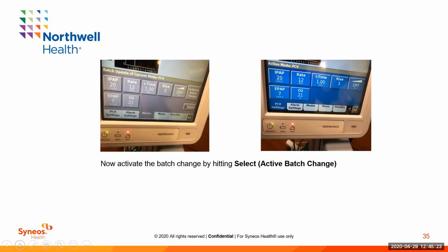Thank you. Okay, so here we have a picture of the batch ST, batch pressure control ventilation settings that Northwell is using. We have inspiratory pressure set at 20, the respiratory rate of 12, inspiratory time, 1 second of breath is pressure over time to activate a volume. We have a rise set at 3, and that's just how fast the breath is going to initially go in. It's kind of a comfort mode that gets adjusted, how active the patient is breathing. We look below, we see EPAP of 7 and FiO2 of 21%.